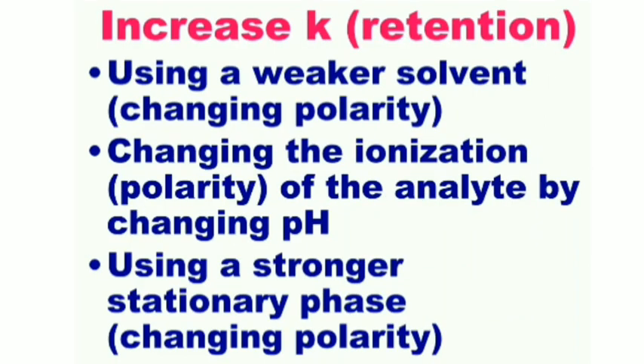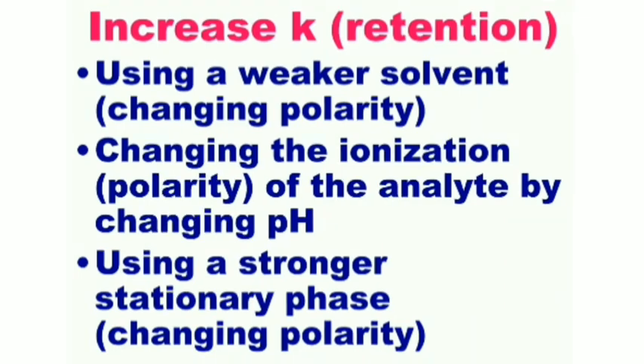Next is increase K retention. You can increase retention by using a weaker solvent, changing polarity, changing the ionization of the analyte by changing pH, and changing to a stronger stationary phase or changing polarity. I hope friends, you have understood how to improve resolution in HPLC. Thanks for watching.